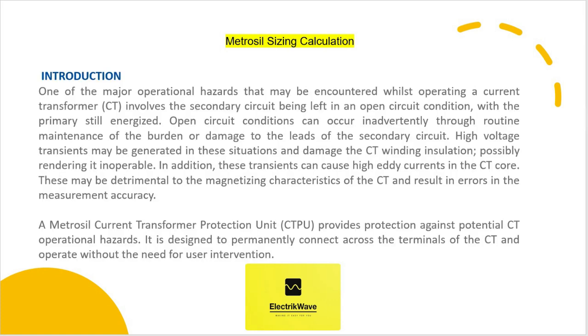Next. Why Metrosil is required? One of the major operational hazards that may be encountered whilst operating a current transformer involves the secondary circuit being left in an open circuit condition, with the primary still energized. Open circuit conditions can occur inadvertently through routine maintenance of the burden or damage to the leads of the secondary circuit. High voltage transients may be generated in these situations and damage the CT winding insulation, possibly rendering it inoperable.